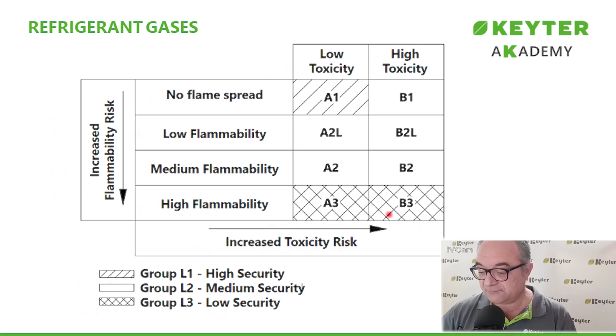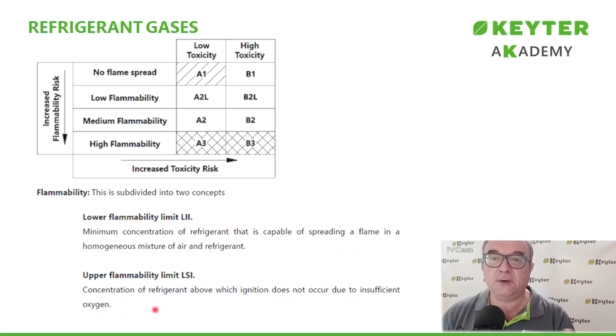What does it mean for a refrigerant to be flammable, or how is its flammability measured? We must consider two concepts. We have to know what the lower flammability limit is, which we will see later, which are tabulated. There is a list where all these parameters are given for each of the refrigerants. The lower flammability limit indicates the minimum refrigerant concentration that can propagate a flame in an air and refrigerant mixture. The upper flammability limit gives the concentration at which there is already an excessive amount of refrigerant, making it impossible to create a flame. Why? Because it has been able to displace oxygen, and without oxygen there is no flame.